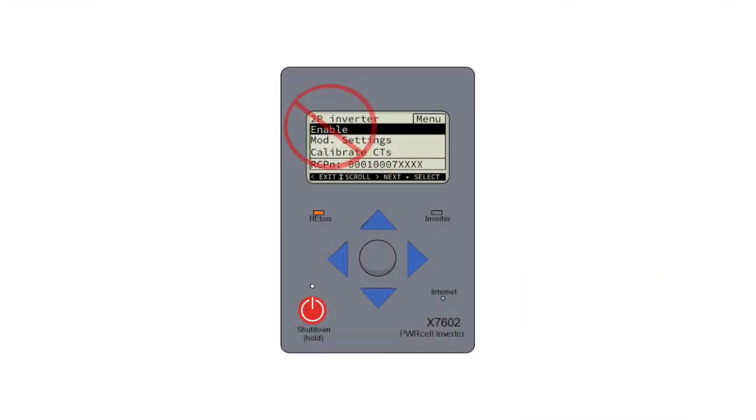If the inverter has been enabled, please disable it before touching the DC disconnects. Also, if this is a multi-inverter system, follow the process spelled out in the Generac PWRcell Inverter Installation Manual, or call our tech support before continuing.